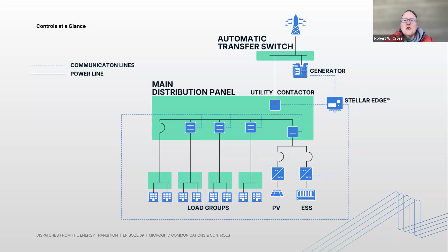And endurance is not even one number. It may be that we need to support these loads indefinitely. Maybe that's really the answer. If so, that means we need a high solar to load ratio for those loads, but that doesn't mean those are the only loads ever supported. If it's a sunny day and the battery is full, we can bring on more loads, and we want to sequence the degradation and return of those loads according to priority. So that's what we talk about, and that trade-off is always there - how long can you go for so much?